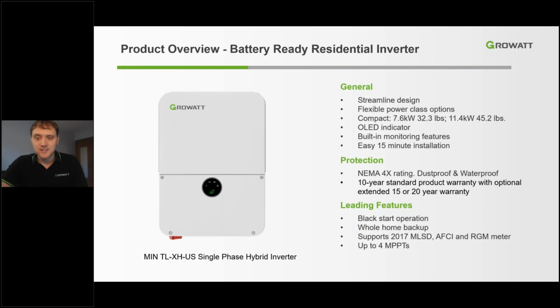The MIN features a whole home backup solution with our SYN microgrid product, supports critical load backup with our automatic transfer switch, supports 2017 module level shutdown with either a TIGO or APsmart transmitter built inside, supports arc fault interruption on the DC side, and has options for revenue grade metering to generate SREC credits in applicable states such as Illinois. The inverter comes in either a V2 or a V3 model, which I will discuss why is important in later slides.